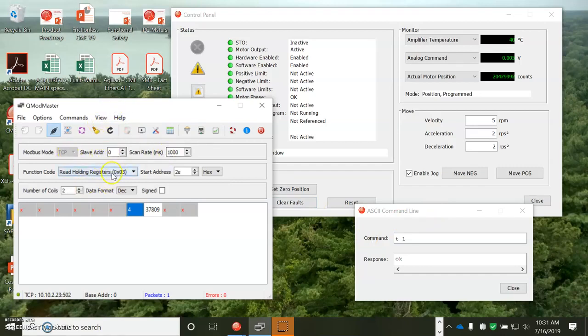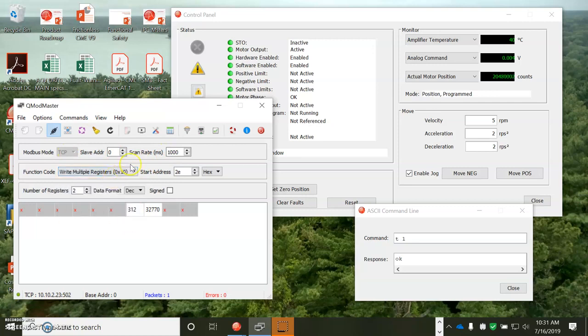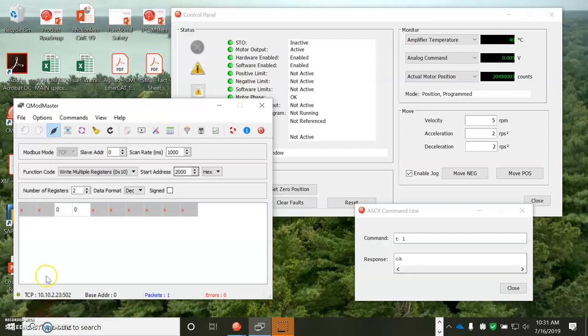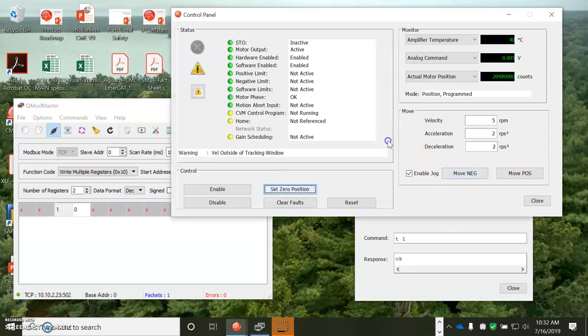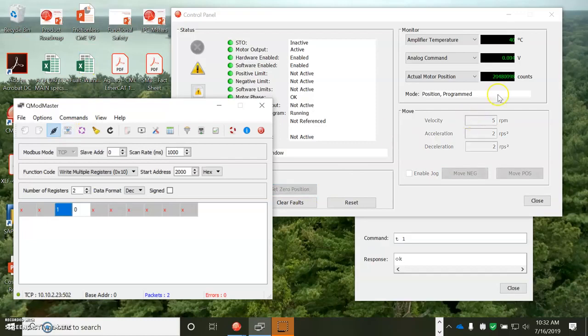So I'm going to do a write to the holding register, function 16 hex, and then 0x2 or 2000, 2000 hex. And put in a number there. Let's set that to zero and update it. And there it makes the move.